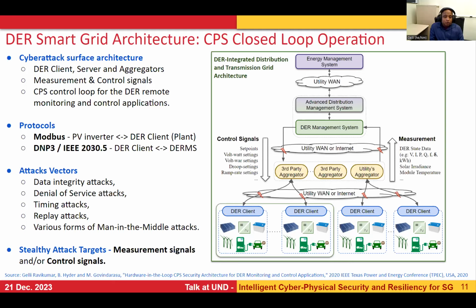The protocols we typically use are Modbus and SunSpec Modbus between the PV inverters and DER clients at the edge devices, and DNP3 or IEEE 2030.5 between DER clients and the DERMS application. There are also other IT protocols like SSH, MQTT, and Kafka, which are currently used between DER clients, DER aggregators, and the DERMS.